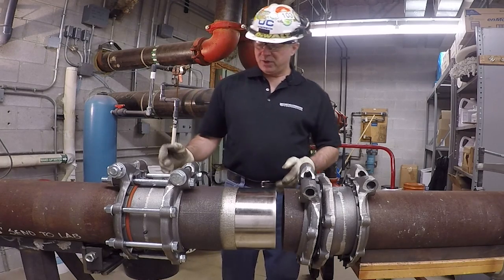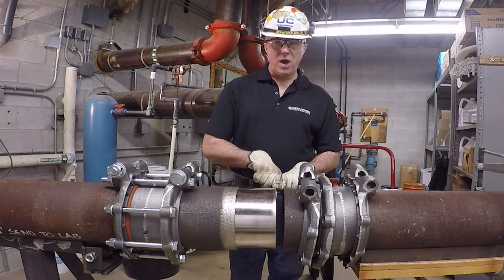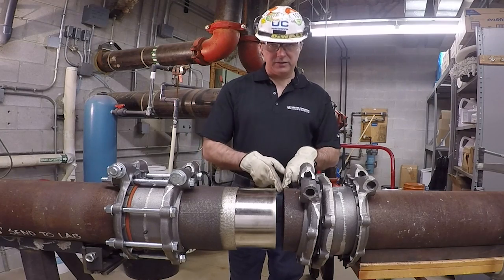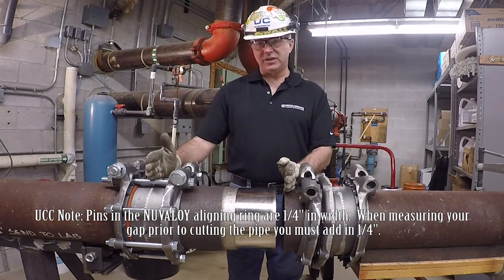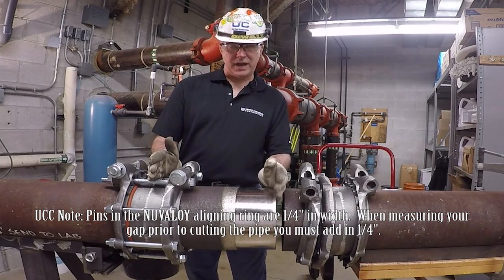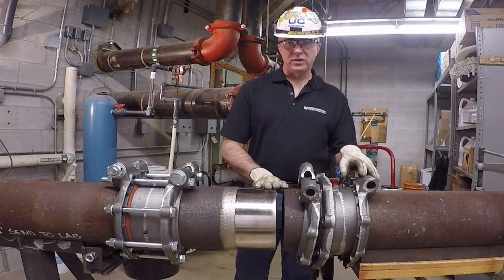For example, the NUVALOY expansion kit body I'm using is 15 inches in length and my gap is one inch. After laying the pipe down, I measured back 16 inches from the end of this pipe and that is where I cut it. Once I installed my 15-inch long NUVALOY expansion kit body, that left me with a one-inch gap, which is critical according to the construction drawings.